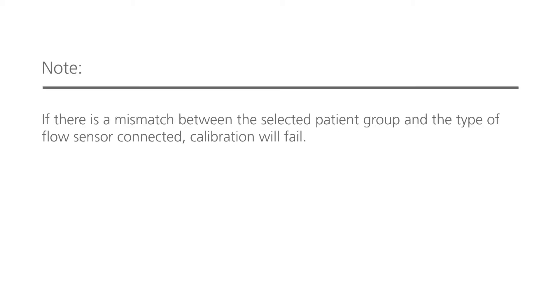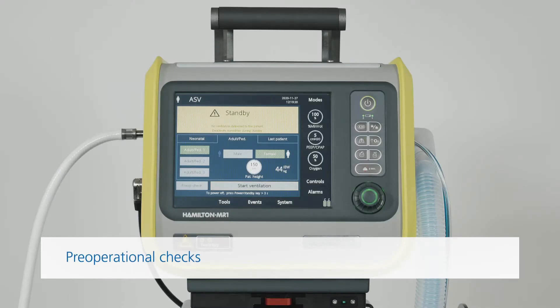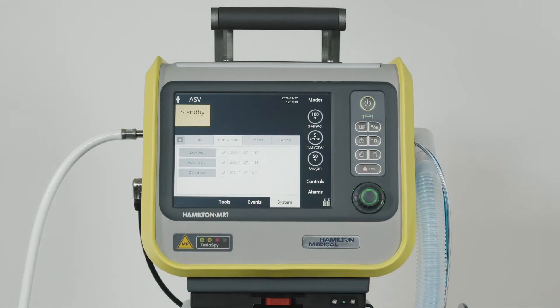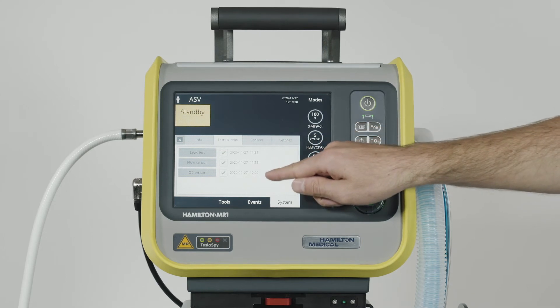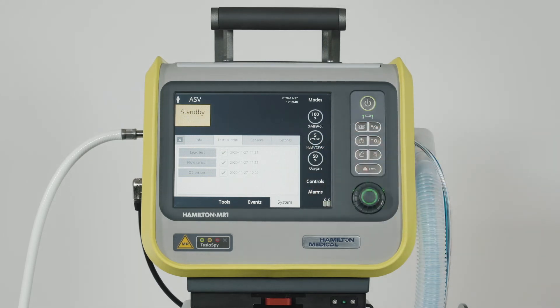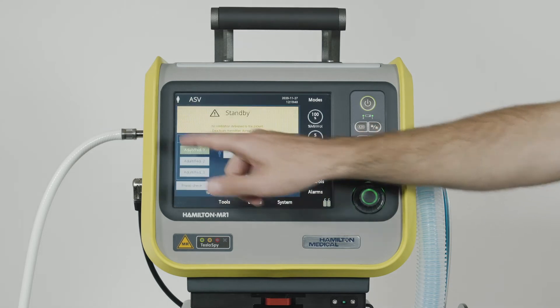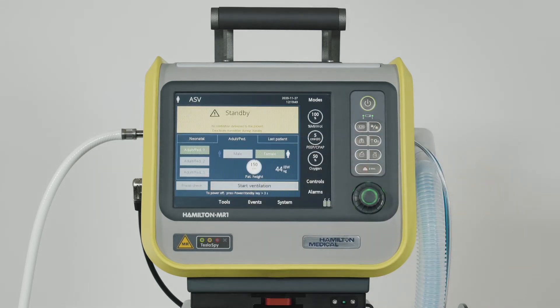If you've already performed the pre-operational checks, you don't need to do them again. The test results are stored in the ventilator's memory, even when it's turned off. Make sure that the setup you calibrated is not changed or altered while the ventilator is in storage. If you haven't already done the pre-operational checks, you need to run them now.